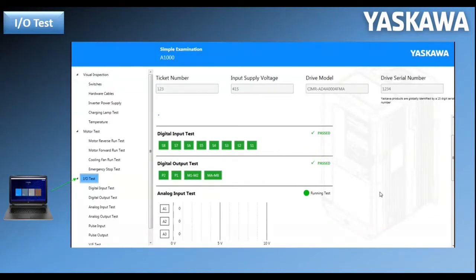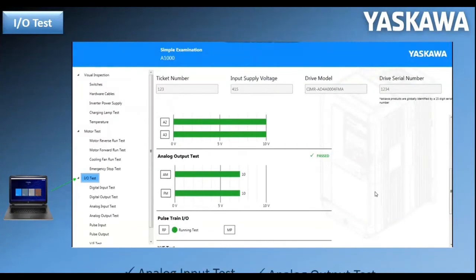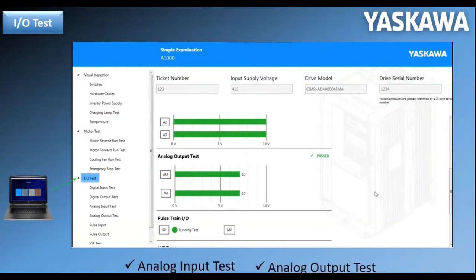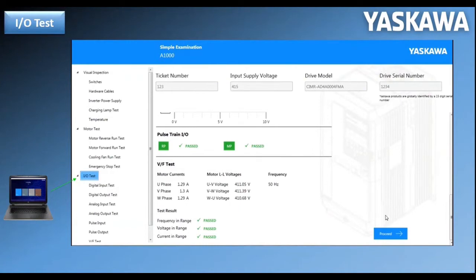The last test is the IO test, which is fully automatic — the user does not need to click anything. It will run through in a completely automatic way and test all input/outputs: digital input, digital outputs, analog input, analog output, and pulse input/output as well. One more test is the V/F test, which will test the application with all phases — whether all phases have the proper voltage and proper current. In that test, the motor will run two times in reverse and two times forward at 50 Hz.